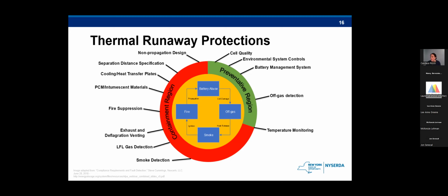If there is off-gassing, the off-gas detection system and temperature monitoring should be able to give warning as well, and you can prevent the system from continuing in the thermal runaway event. Once the system starts to smoke, you're really now in containment mode as the system is in a thermal runaway event. As you can see, as the timeline progresses, there are more safety measures in place to contain the event. And you'll hear more about each one of these controls as we go through the code.